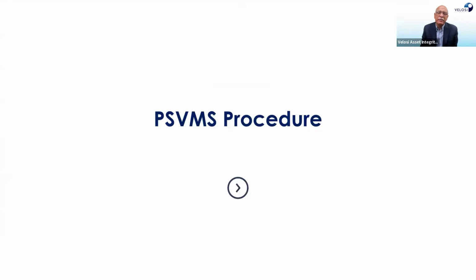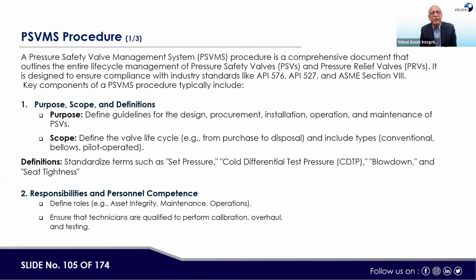So the PSVMS procedure, what it covers. PSV: pressure safety valve management system. Here, purpose, scope, and definition. The purpose is to define guidelines for design, procurement, installation, operation, and maintenance of the PSVs. The scope is also the same: define the valve life cycle, for example, from purchase to disposal, and include all types: conventional, bellows, pilot operated, all types of the valve.